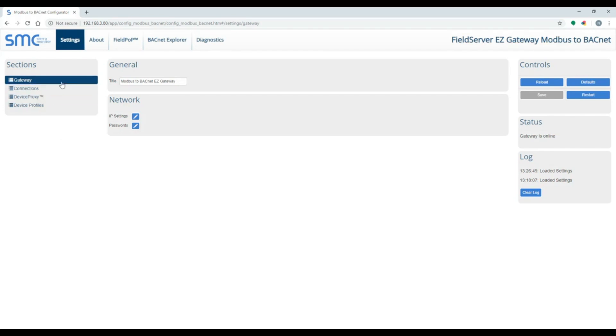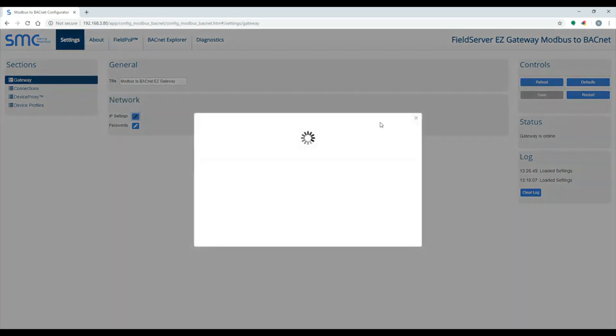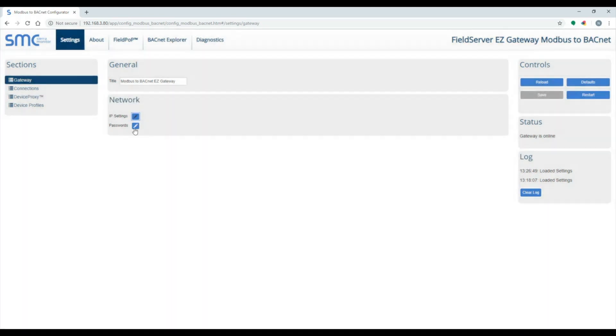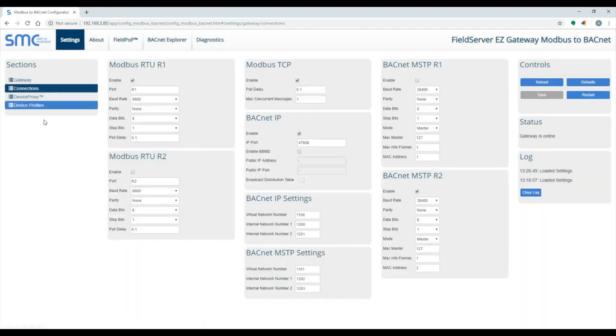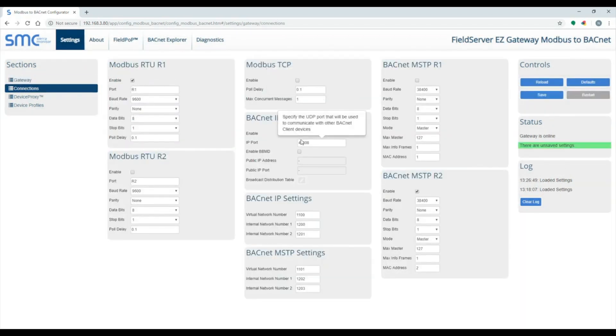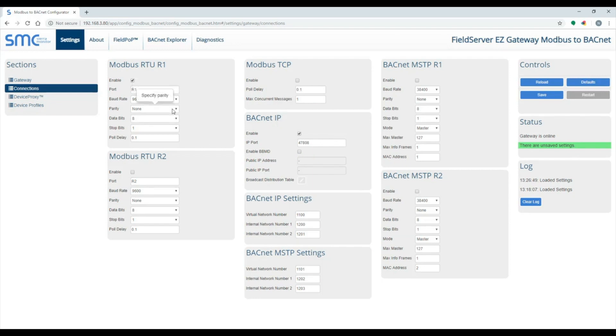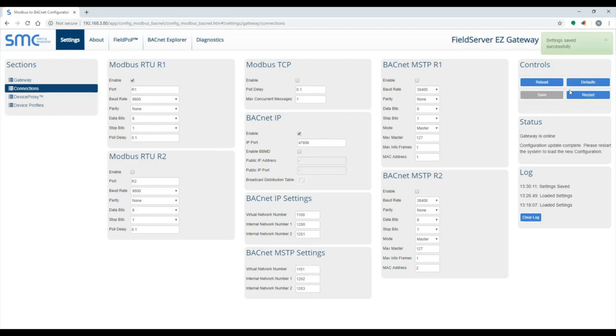The Gateway section of the Settings tab is used to assign a title to the gateway, change the IP address, and enable a password. The Connections section is for setting up the Modbus and BACnet connection. For this example, I will use Modbus RTU and BACnet IP. I disable the unused connections. After updating, click on the Save button and the Restart button.